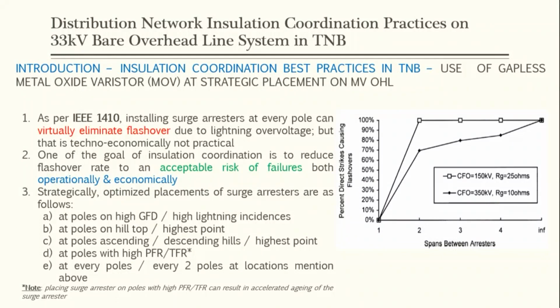One of the goals of insulation coordination is to reduce the flashover rate to an acceptable risk of failures, both operationally and economically. Strategically, the optimal placement of surge arresters is as follows. One, at poles with high ground flash density or high lightning incidence; two, at poles on hilltops or the highest point; three, at poles ascending or descending hills; four, at poles with high pole footing resistance or tower footing resistance. Only that placing surge arresters on poles with high PFR or TFR can result in accelerated aging of the arrester. And at every pole or every 2 poles at the locations mentioned above. So we put either every pole or every 2 spans, at the locations mentioned in A, B, C, and D.